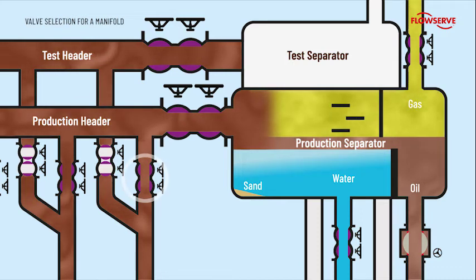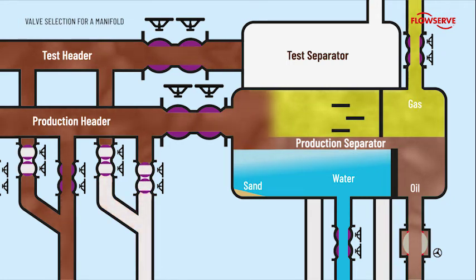For this operation, the targeted flow line valves are closed and the flow line is bled, whilst the other wells remain in production keeping the header under pressure. To avoid a full shutdown, whilst ensuring the operator's safety when they work on the flow line, a double block and bleed system is required, so isolation can be verified.